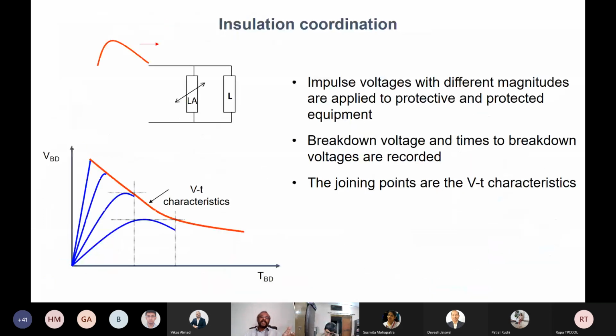Now, it's very important that when you are selecting a lightning arrestor, and this is another thing, that in medium voltage and high voltage systems the surge protective device or SPD is called the LA or lightning arrestor. When you are selecting a lightning arrestor, it is very important that you should have some idea about the VT characteristics. What are VT characteristics?